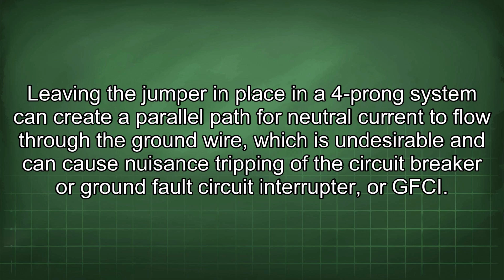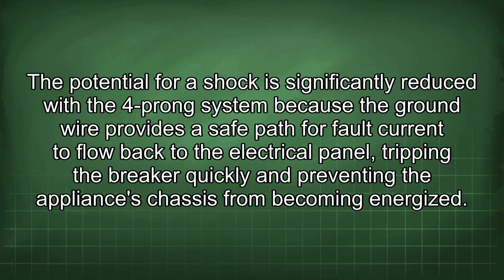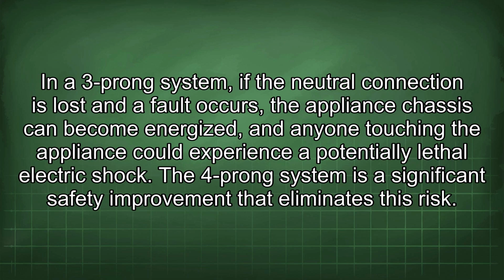The potential for a shock is significantly reduced with the four-prong system because the ground wire provides a safe path for fault current to flow back to the electrical panel, tripping the breaker quickly and preventing the appliance's chassis from becoming energized. In a three-prong system, if the neutral connection is lost and a fault occurs, the appliance chassis can become energized, and anyone touching the appliance could experience a potentially lethal electric shock. The four-prong system is a significant safety improvement that eliminates this risk.